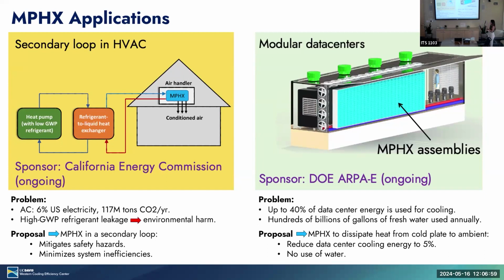So here we are proposing, first of all, designing a cold plate that will dissipate the heat from the chips, so the CPU, GPUs, etc. And then from the cold plate, we will dissipate that heat to the heat exchanger, and the heat exchanger will dissipate it to the atmosphere, the MPHX that I'm talking about right now. With this application, we are aiming to reduce the data center cooling energy to 5%, and also water won't be required in this application.